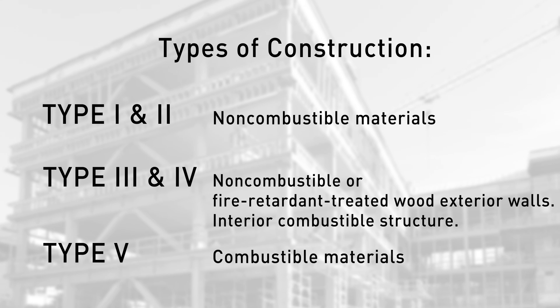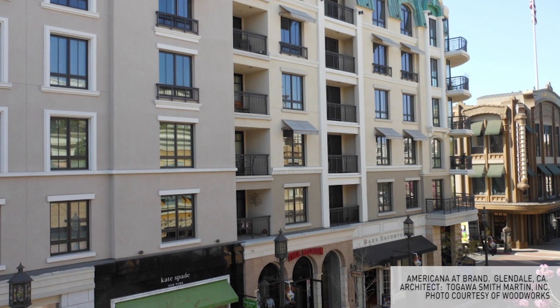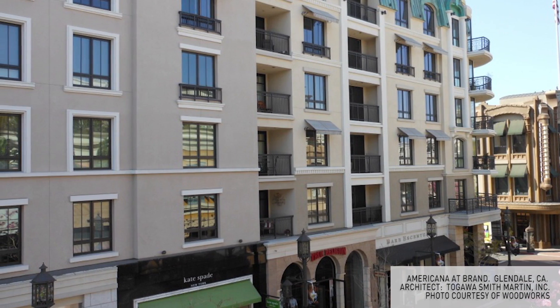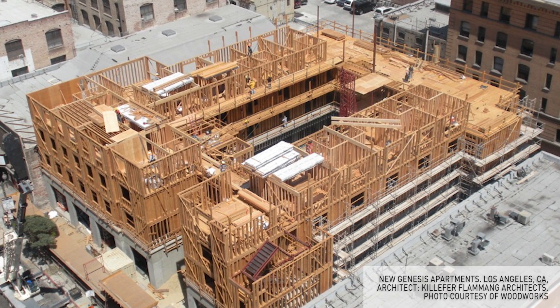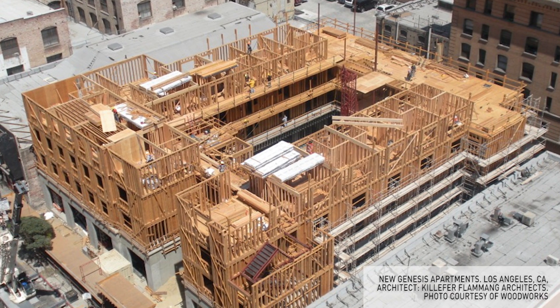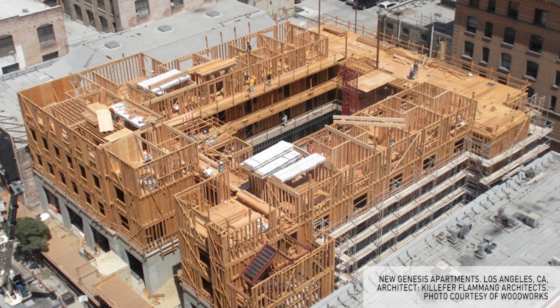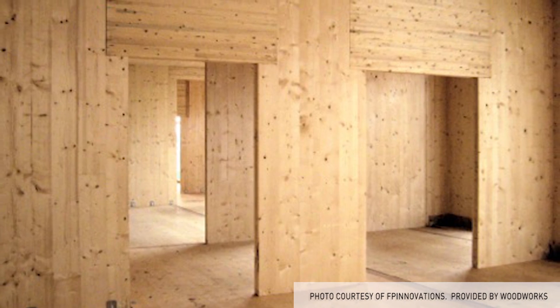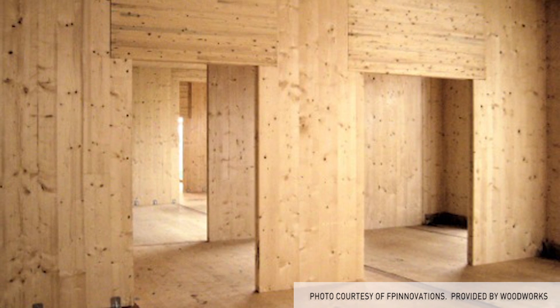Wood can play a role in most of those types of construction. In Type 3 construction, there's an exception in the code that allows fire retardant treated wood on the exterior of the wall. So basically, a Type 3 construction can be an all-wood building.